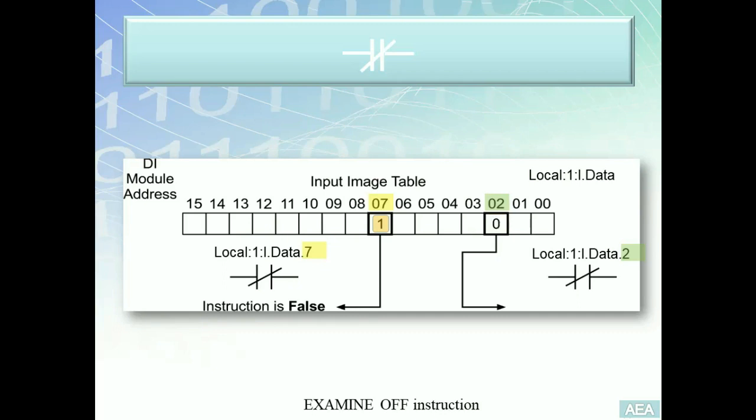That's how we know this XIO will examine terminal number two—is it open? Is it reading a logic zero? The answer, as you can see, is yes. That's why this instruction, wherever it exists in the program, will be currently true and will show the green bars on both sides of the instruction.